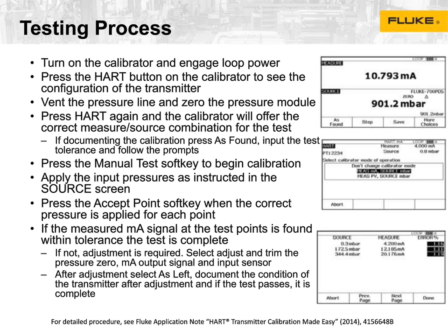At that point, you basically will apply the input pressure. So whether you're using a pneumatic, a gas, or a hydraulic pump, you'll go to the first test point. And once you get there, you hit accept, and then you do that for each point on the test. So if you're doing a 5 up, 5 down, you'll do 5 points up and then 5 points down. And then basically you'll measure, and if the measured signals are within tolerance, you're done. You basically have done an as found test.